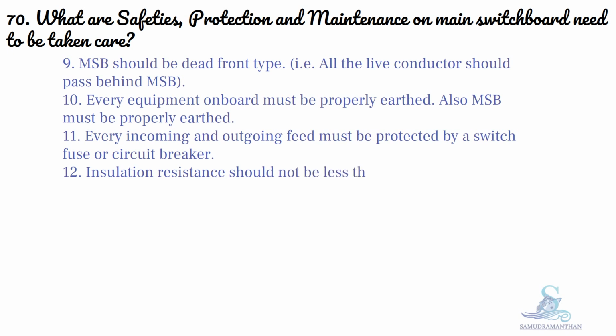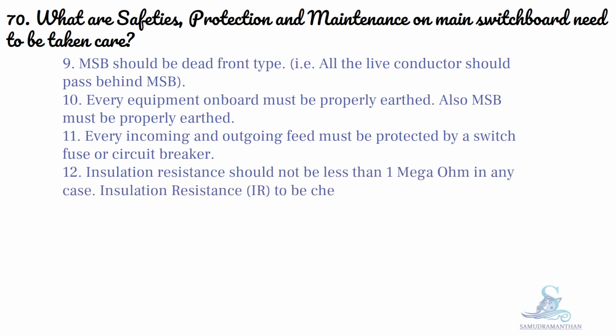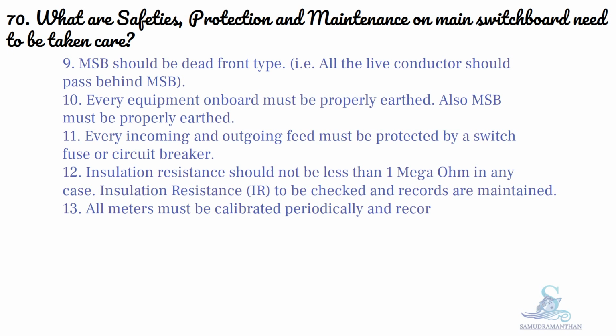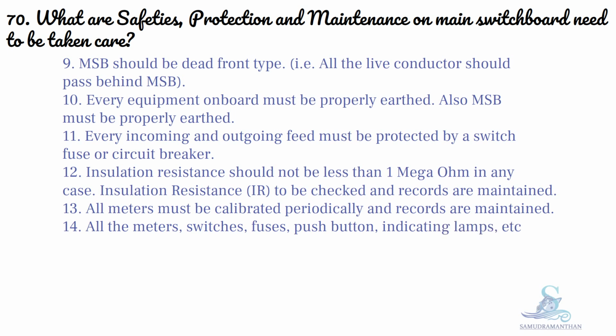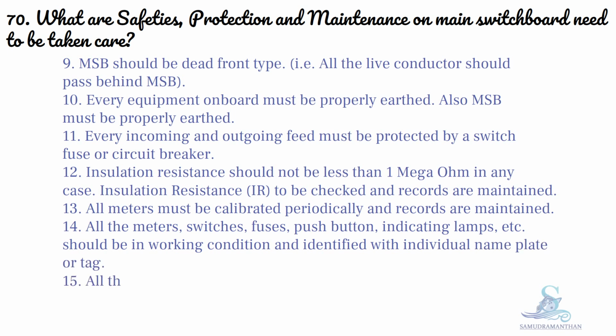Insulation resistance should not be less than 1 megaohm in any case. Insulation resistance is to be checked and records maintained. All meters must be calibrated periodically and records maintained. All the meters, switches, fuses, push buttons, indicating lamps, etc. should be in working condition and identified with an individual nameplate or tag.